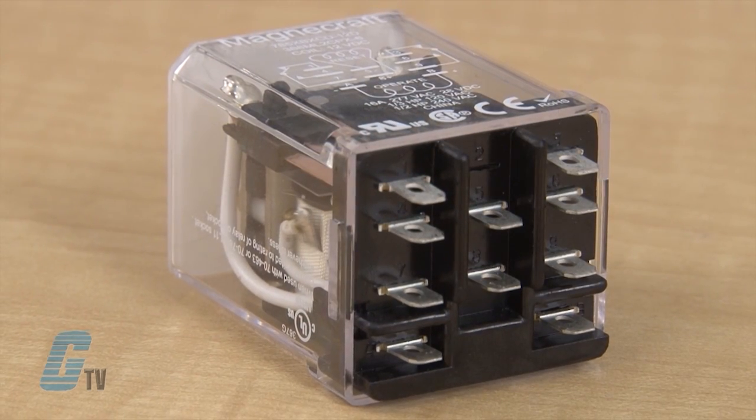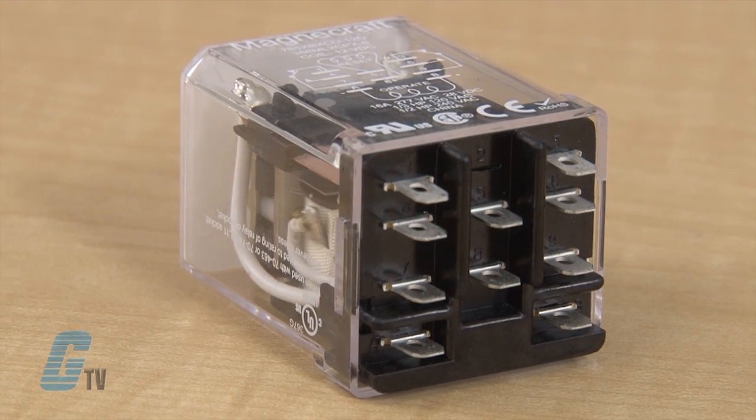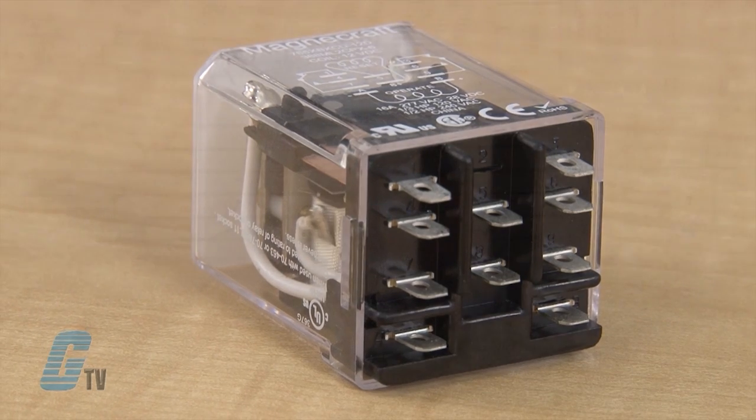The high strength magnetic latch helps contacts hold during vibration. It has 16 amp switching capabilities with a maximum switching voltage of 300 volts. The contacts are made of silver alloy and are double pole, double throw. A permanent magnet maintains the last position until a redirected second pulse moves the contacts back to the original state.